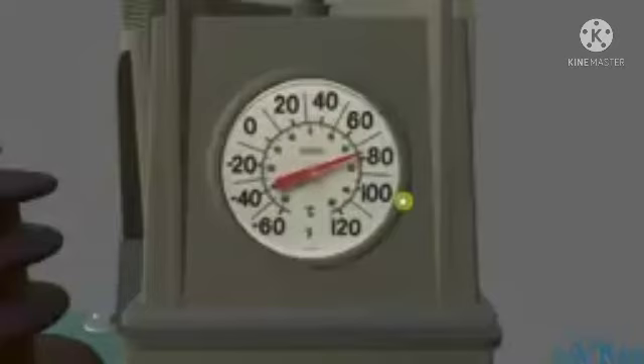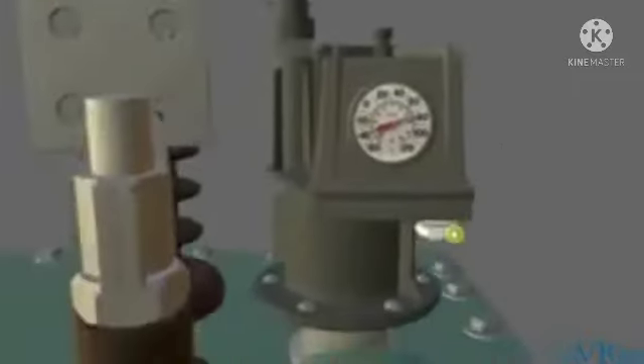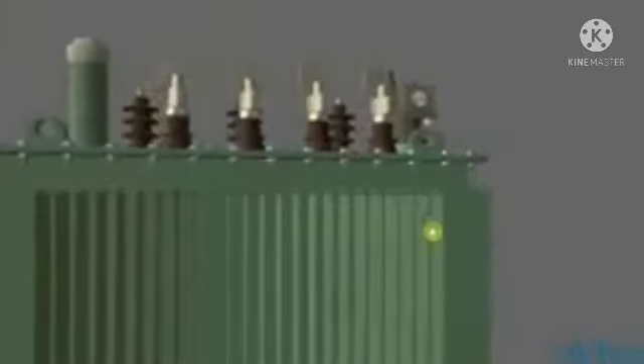And that's going to measure the temperature of the insulating liquid, which again might be mineral oil, or perhaps it will be silicone, or perhaps it will be some sort of synthetic ester, which is more or less a biodegradable oil manufactured from plants. If we zoom out, we can see that the casing itself is not perfectly square. It's got these fins attached to the side. These fins are used for cooling the transformer.